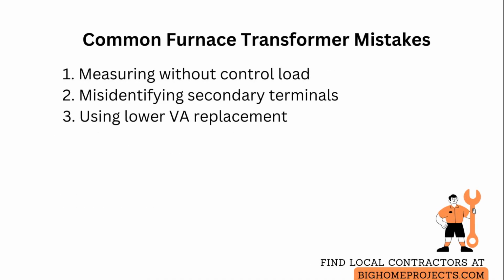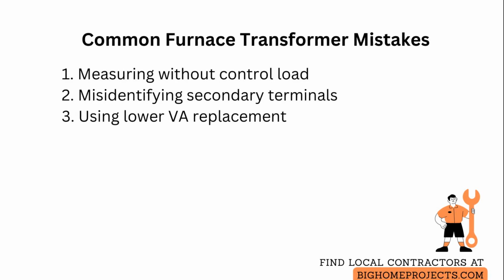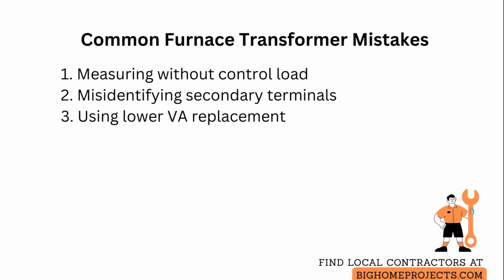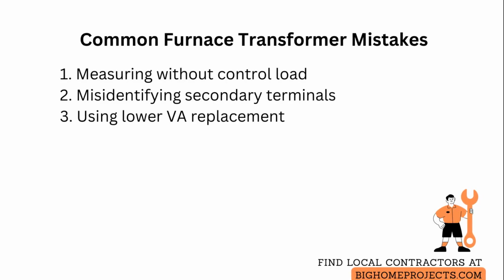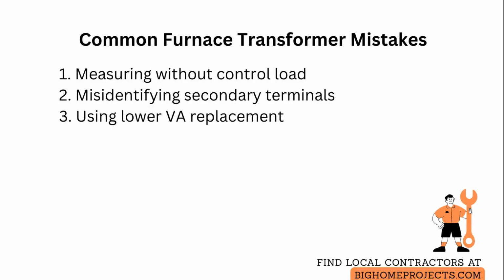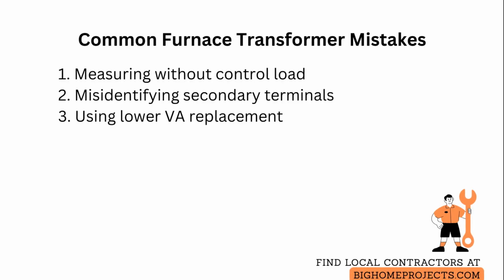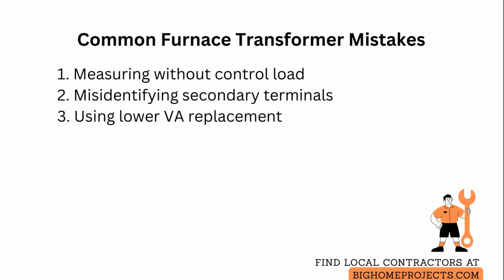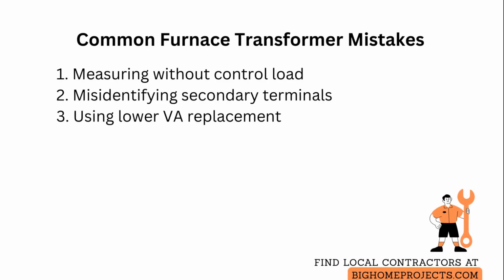Common mistakes include measuring voltage without applying the control load, which can show normal open circuit voltage and mask internal weakness. Remedy this by measuring while the system is actively calling for heat. A second issue is misidentifying the R and C terminals on multi-winding transformers or power distribution boards, leading to incorrect measurements. Resolve by tracing wires back to the transformer secondary or consulting the wiring diagram and labeling terminals before testing.